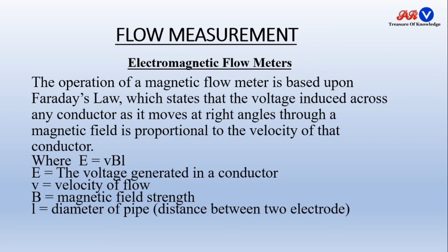Now, the working of the electromagnetic flow meter. This is the construction part. The figure shows the electromagnetic flow meter. Here, this is the tube through which our fluid for flow measurement enters, and these are two magnetic coils on which we apply some voltage to produce a magnetic field, which is perpendicular to the conductor path, and these are the two electrodes which are used for getting the output, which is proportional to the fluid velocity.